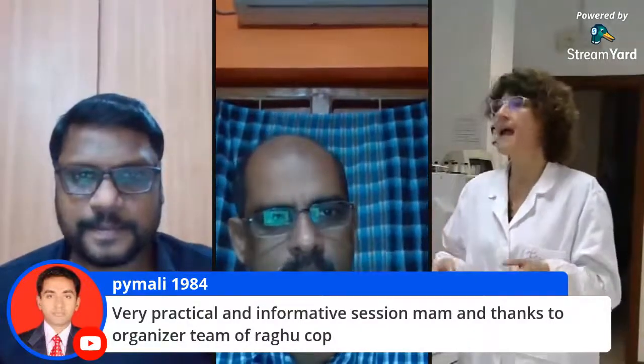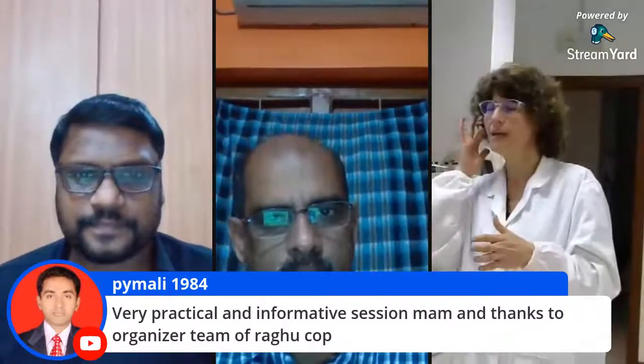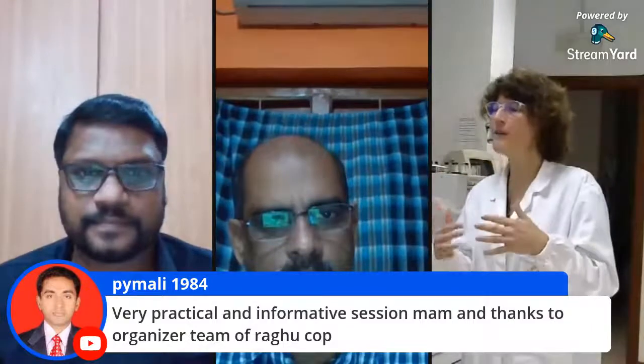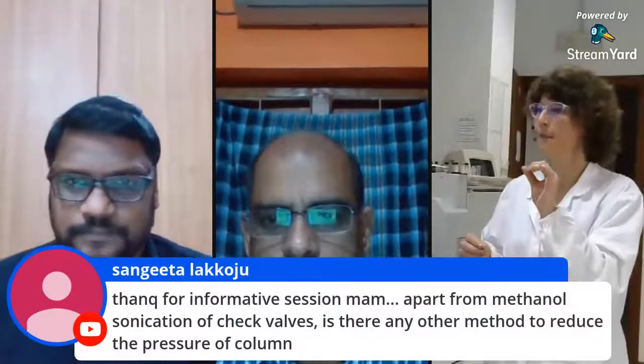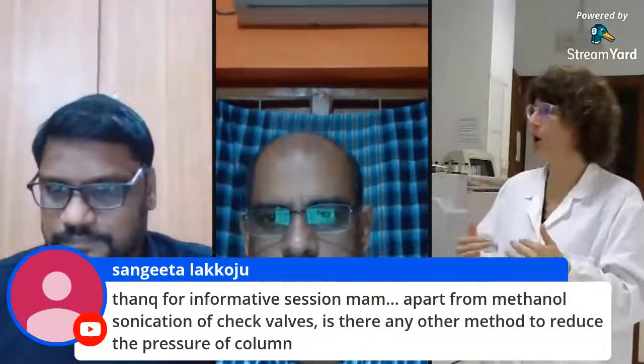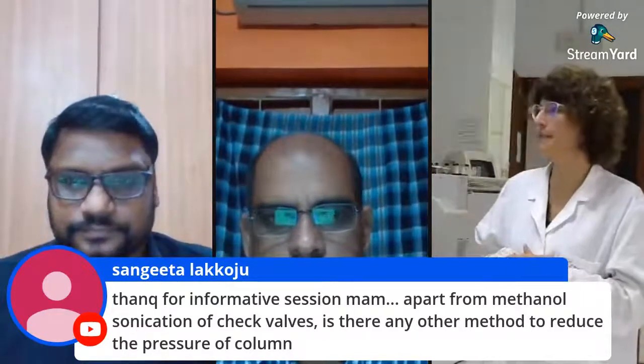So this is one way, and another way, if you have a mass spectrometer detector, for example, is to extract an ion of interest, filtering out all the ions that are only background noise. I hope it is clear. Or perhaps you can also use a constant temperature in the detection cell, in the conductivity cell. The thermostating of the conductivity cell would be another major way to decrease the background noise, obviously.